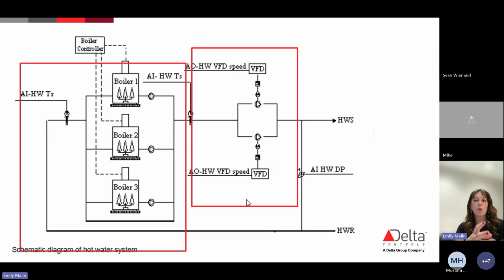Basically, this is using pumps and VFDs, that's our variable frequency drive. We saw the same thing in our VAV and air handling unit. But what's happening here is that pumps are pushing all of that hot water through the pipes inside of our building into the radiators in order to release heat into a space. As our water moves, it's going to carry all that heat to different parts of the building, right? So what we're seeing here are flow sensors. We're going to see pressure sensors, ensuring that all of our water is moving correctly into the room and into the zone.